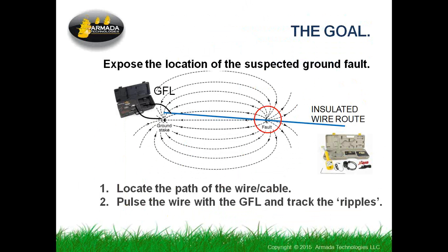That's the whole thing, is we need to get out there and figure out where some damage has occurred or potentially occurred. Sometimes the damage is intermittent. It only appears when the ground is wet or that it's been watered, for example. When it's dry, it's not there. Very common problem with bad splices and nicks in insulation as opposed to completely cut wires. When you're doing this, number one, you have to locate the path of the cable. So get your locator out, or maybe someone else has done it. Find out where the cable's running, and then begin to do the wire pulsing with the GFL. And we'll show in a second just how that goes on and how that works.